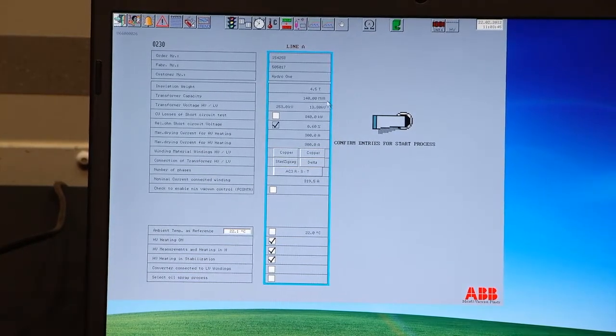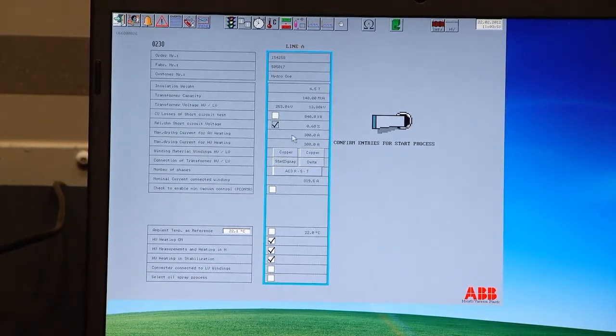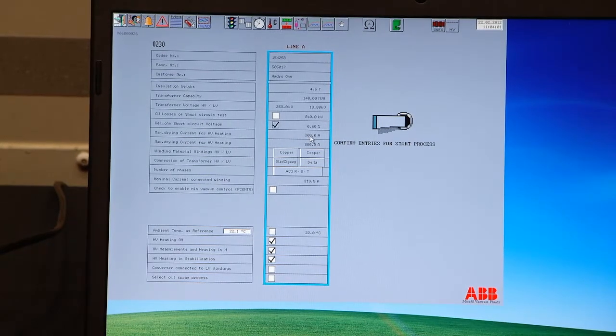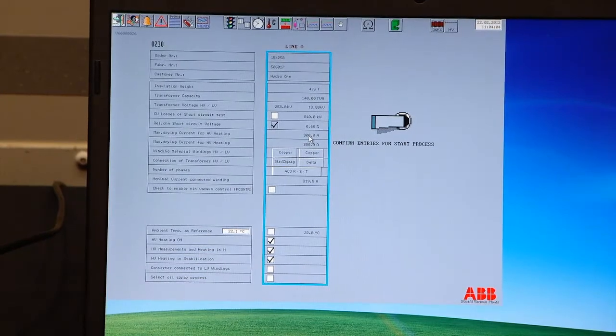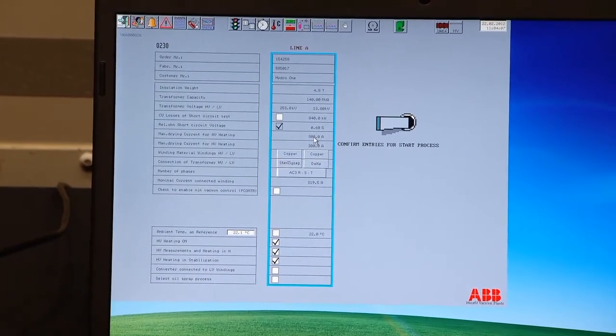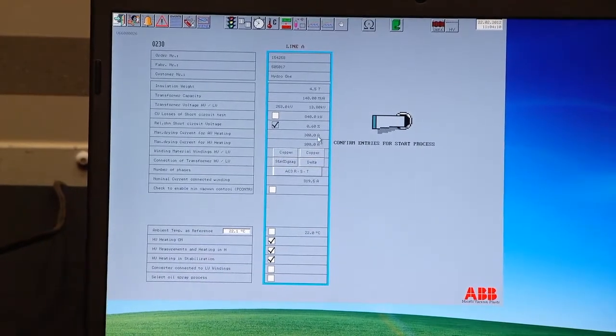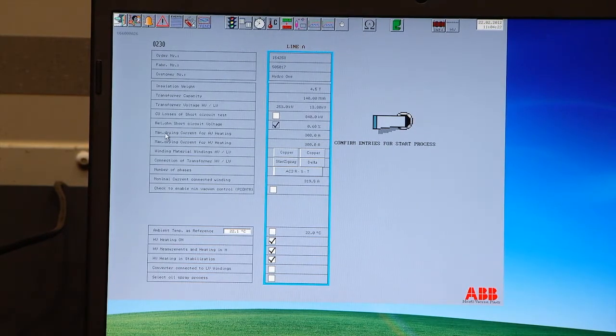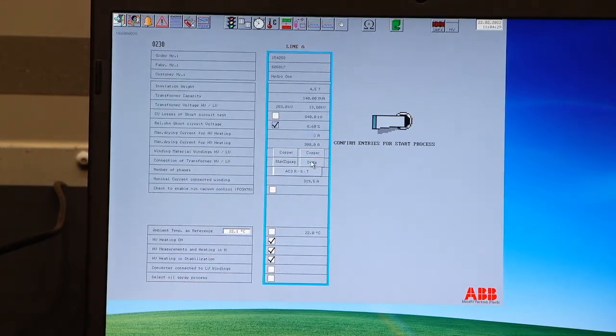Then, when we have entered these values correctly up here, we come down to our maximum drying current for the heating. This is a safety factor. I will show later a little bit what's happening with the current factor and things like that. But this is to make sure that this value is never exceeded. The nominal current for this transformer is 320 amps. Let's say that we want to dry at about 50% of the nominal current, that's 150 amps, 160 amps. But if we make a mistake or anything, we never want to exceed 300 amps. Let's say so. You enter 300.